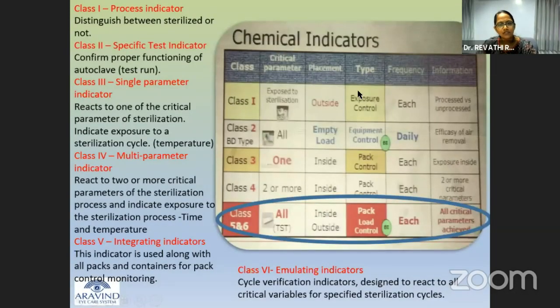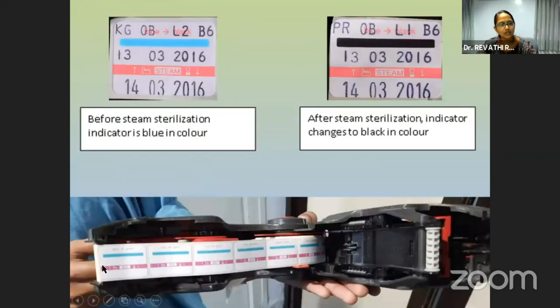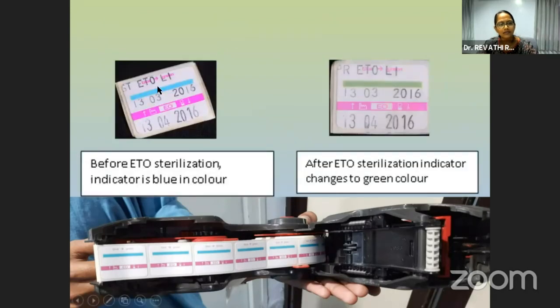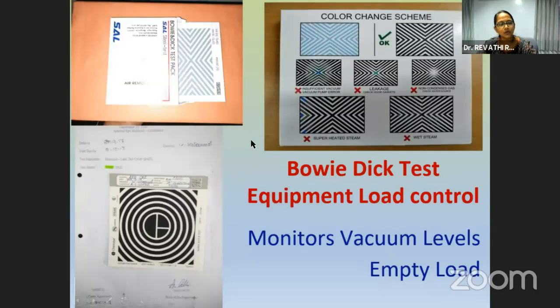Coming on to the indicators, which tell us about the quality. There are 6 indicators. It's not hierarchy-wise. The class 1 indicator, class 2, class 5 and 6 are the crucial ones. The class 1 indicator is a simple 3-line indicator. It just says that the product has gone through the autoclave. It doesn't say that the sterilization process parameters have been met. So any color change for the steam sterilizer from blue to black, or for an ETO from blue to green, means that the pack has gone through the sterilization process.